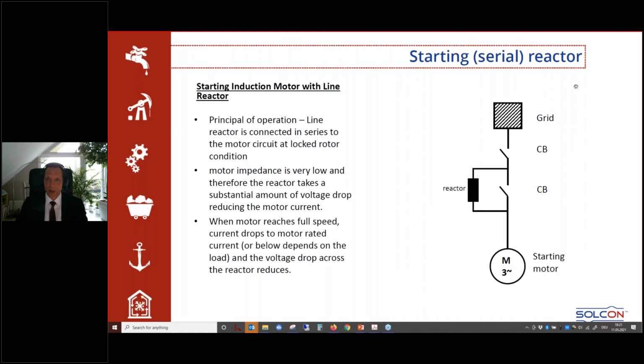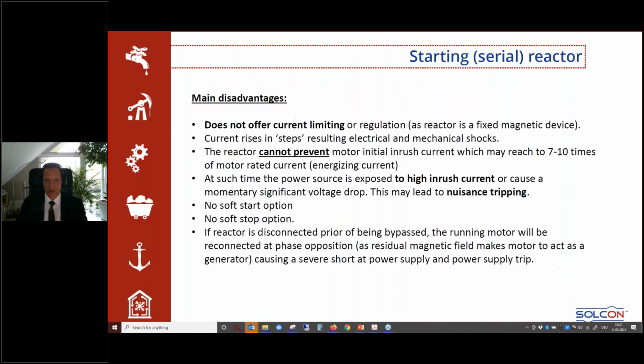What we also can do is to have a so-called serial reactor. You have this circuit breaker open, this circuit breaker closed. You have the current flowing through the reactor and through the motor. This is taking a certain part of the voltage. The motor sees reduced voltage. It is possible, but has some disadvantages because you still have a high inrush current in the reactor. So the dynamic inrush current is not reduced, and this may lead to tripping. And this is if the reactor is disconnected prior to being bypassed, the running motor will be reconnected at phase opposition, and motors do not like this either.